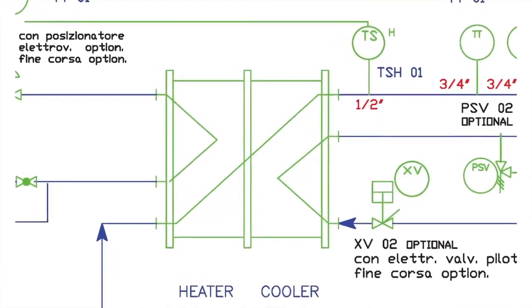Why is this necessary? In practice, with this trick, we are able to extend the plates, meaning we have a much higher thermal length of the plates, practically double compared to the height of the heat exchanger. This allows us to push the recovery, the intersection of temperatures, to very high limits.